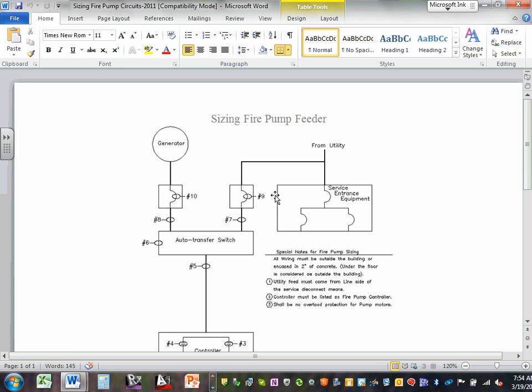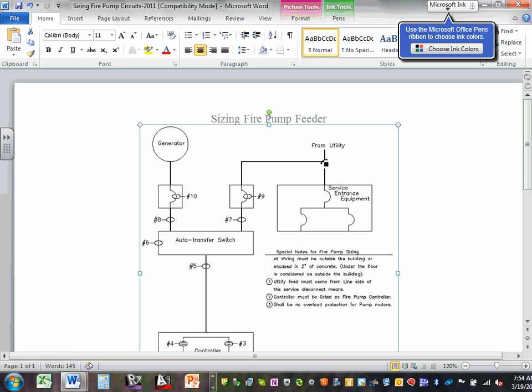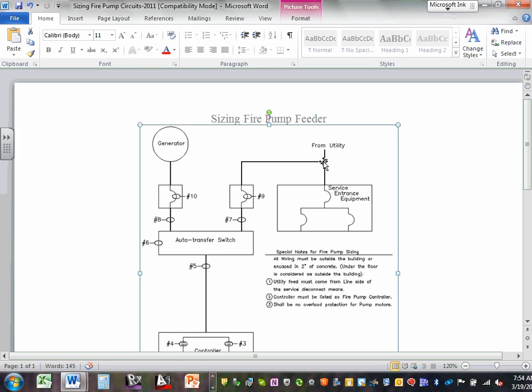Number 7 is when you have a fire pump, you have to have 2 sources of power for the most part, right? One source is coming from the electrical utility, and another source is coming from the generator. On the electrical utility side, you feed it from the line side of the overcurrent protection device. Can you see where the feeder is, not from the panel, from the line side. Here's the circuit breaker, you feed it from this side, not here. So from the line side.